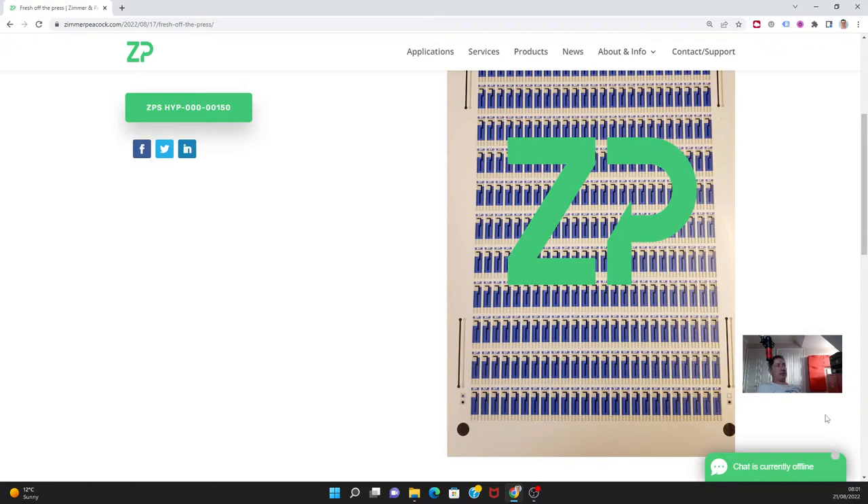Being the best has to have some context. This electrode is made on a polymer, which means you can't necessarily use it with organic solvents — you couldn't leave this sensor in a bath of DMF (dimethylformamide) or THF (tetrahydrofuran) because it would eventually dissolve. You could use those solvents briefly to cast upon it, but not for prolonged immersion. So when I say it's the best, the context is: great repeatability, great surface, good for biosensing and electrochemistry in the aqueous phase.